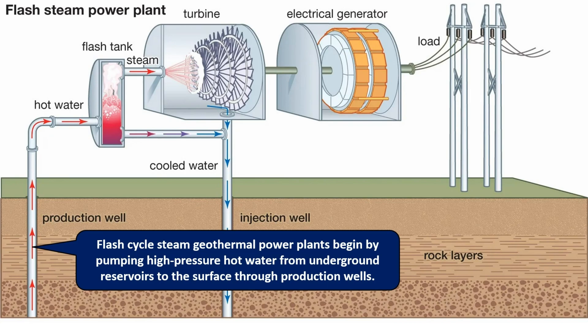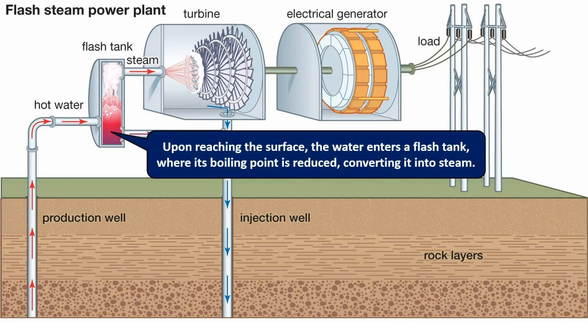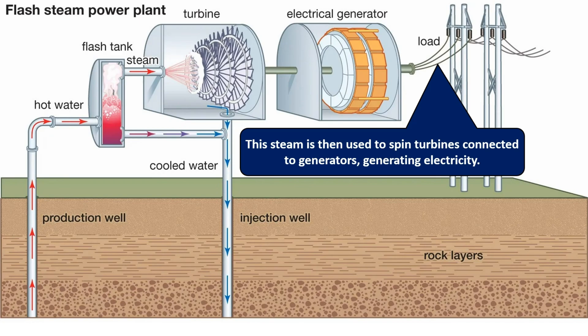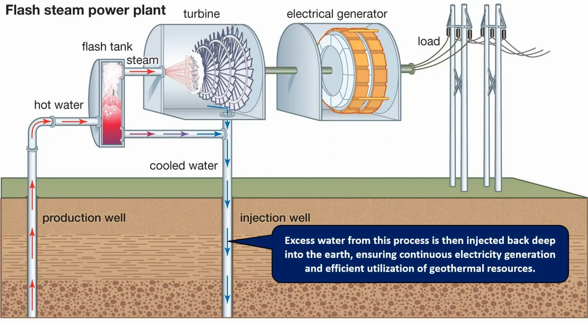Flash steam geothermal power plants begin by pumping high-pressure hot water from underground reservoirs to the surface through production wells. Upon reaching the surface, the water enters a flash tank, where its boiling point is reduced, converting it into steam. This steam is then used to spin turbines connected to generators, generating electricity.